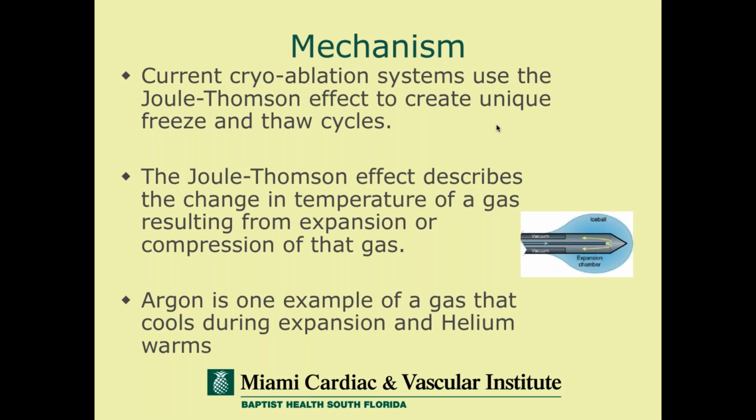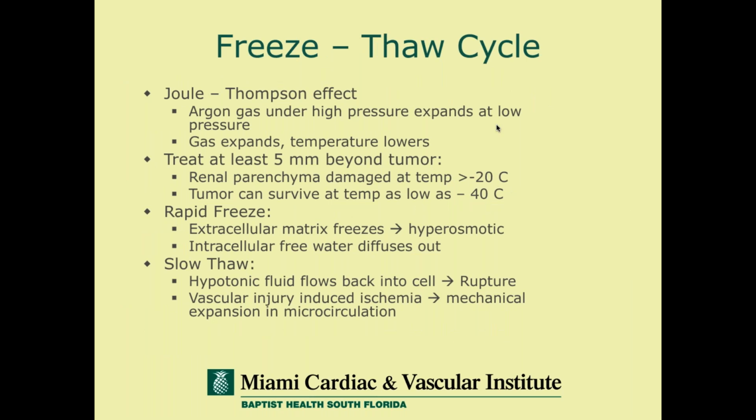But the way cryoablation works basically is based on the Joule-Thomson effect, that as you freeze and thaw gases, they expand and compress. And when they expand and compress, you have a huge change in temperature. As they expand these gases, they really create a huge cooling effect, and they can create that ice ball. What we see really is using the traditional gases or argon that cools during expansion, then helium, which we use to warm or thaw and create that thawing effect.